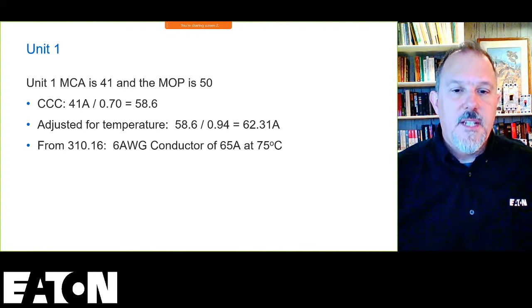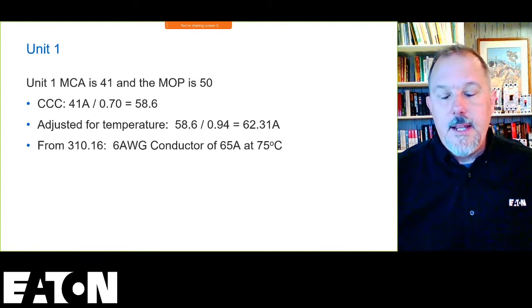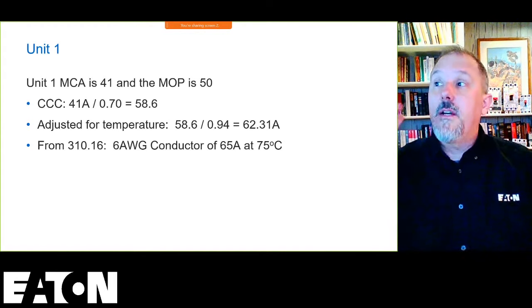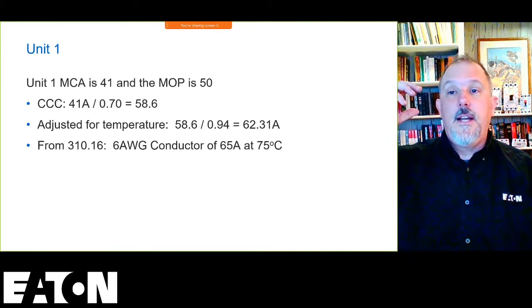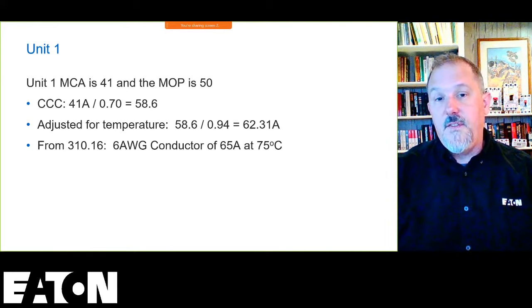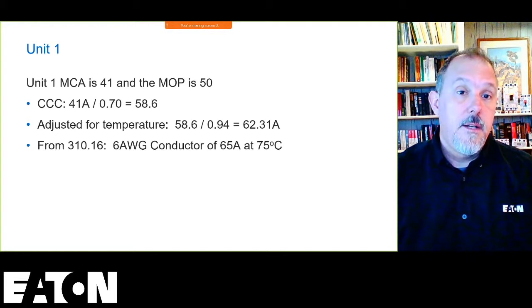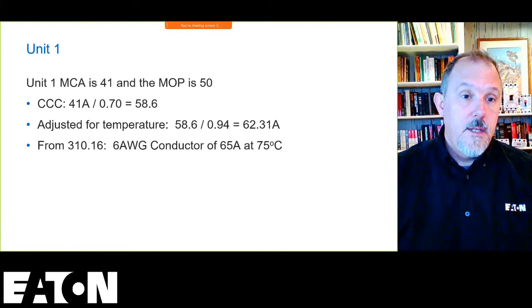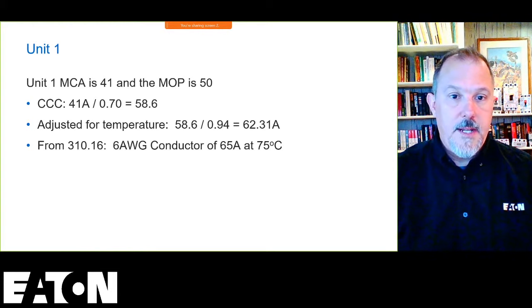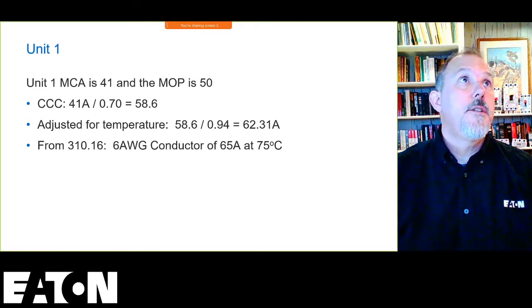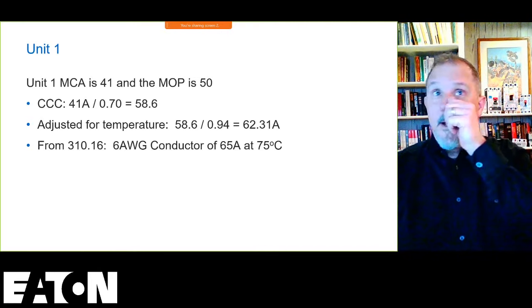Yep, the ampacity from the 75 degree column can be used for derating. Yes, because it's in a wet location and I am using THWN, THHN, I am basing my numbers off of the 75 degree C column. All right, I'm going to look on Facebook to see if anybody out there disagrees with my numbers, with my number 6.